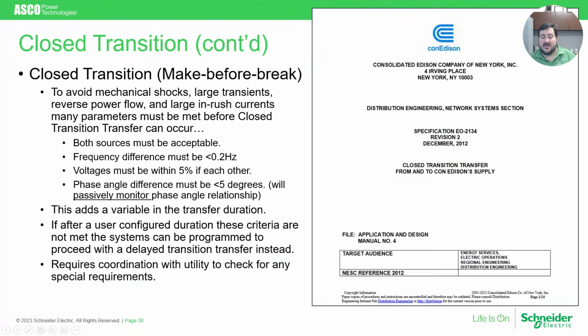The frequencies must be matching within less than 0.2 hertz of each other. The voltages must be within 5% of each other. There cannot be a phase angle difference greater than 5 degrees. And all this is done by monitoring the two sources relative to each other passively.